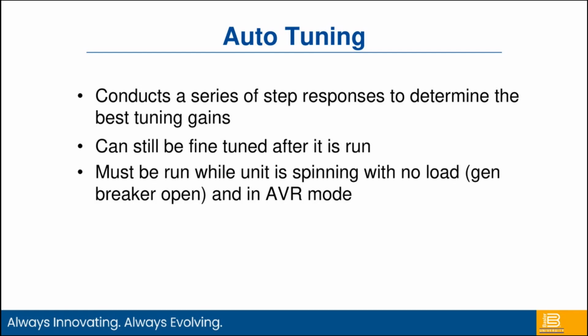One of the features that Basler has implemented on our digital products, our digital voltage regulators, is an auto tuning function. So what we do is we conduct a series of small step responses. We'll basically input pulses out into the exciter field, and we'll look at the response of the machine. So the voltage regulator, by looking at the response of the machine, can internally calculate the time constant. So it knows when it put the output into the exciter field, and it looks at how the generator reacts. So we can calculate those gains automatically, and then we can always come back and fine tune it later. So those gains will get us a good response, a stable response, and then we can come back and just tweak those gains to get the response we want.